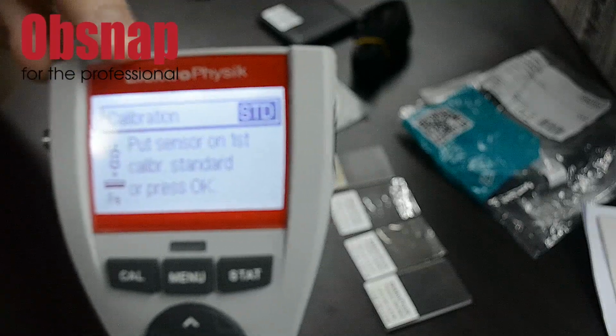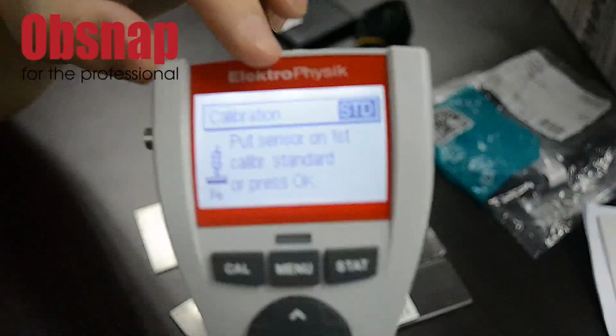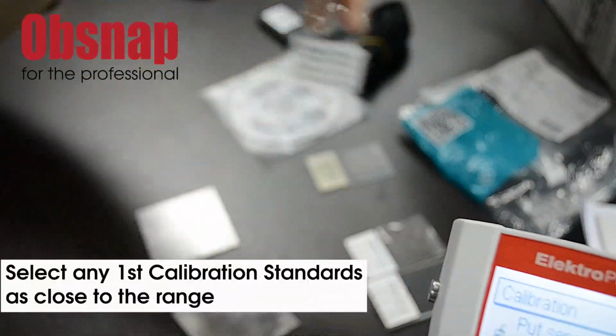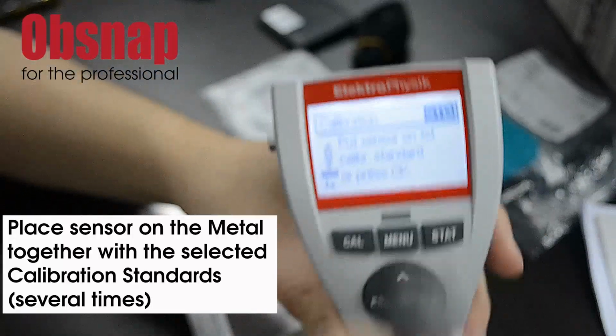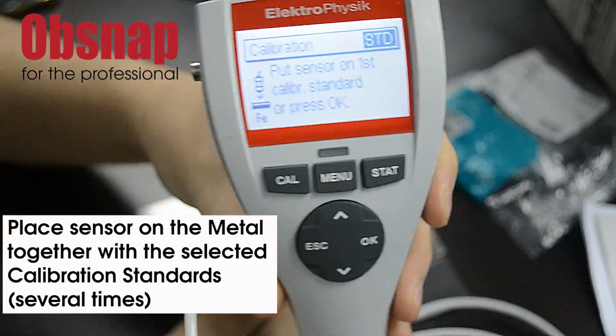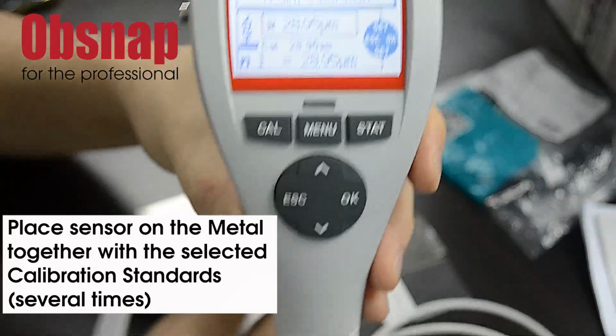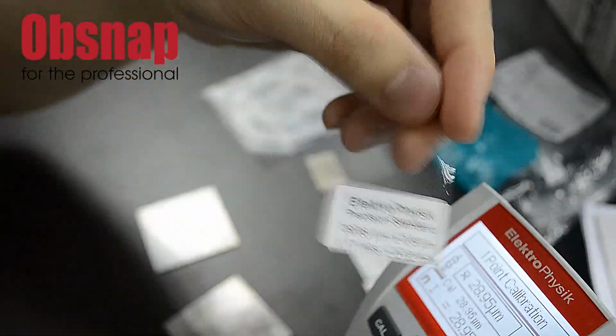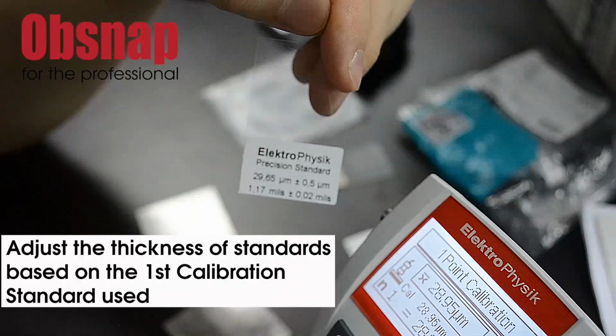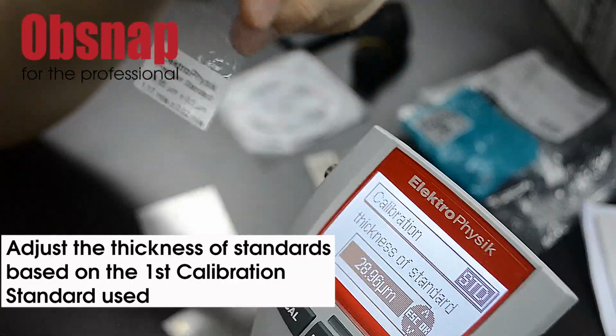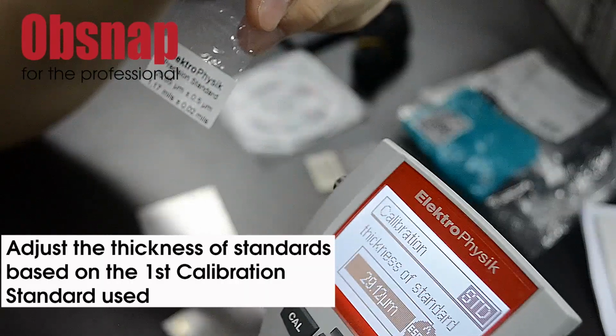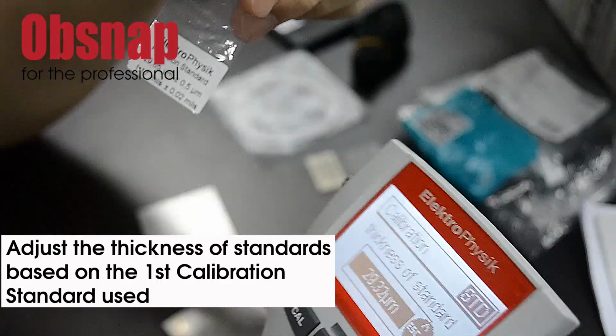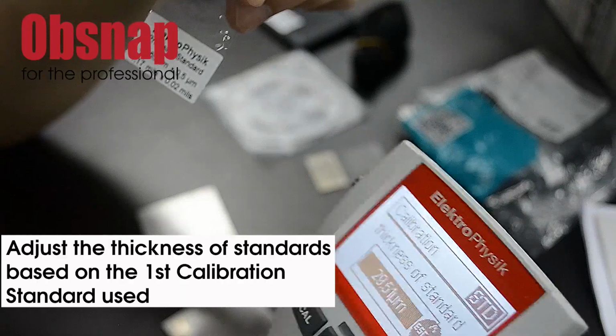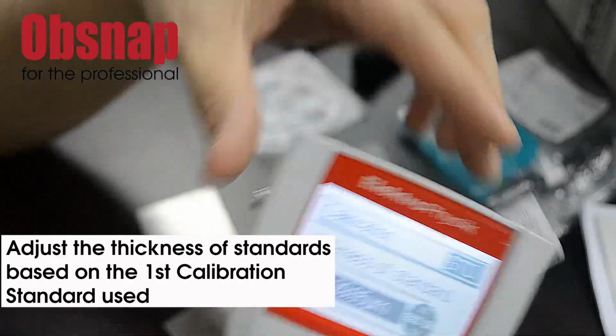Then it asks you to put the sensor on the first calibration standard and press OK. Right now you can choose any calibration standard that's close to your range. So just place it on the metal, and same, put the probe on top of the calibration standard. And you will get a reading. Next, we can adjust it to be the same as the standard given. So it's 29.65. You can press the up down button and adjust it. 29.65 micron. Then we press OK.